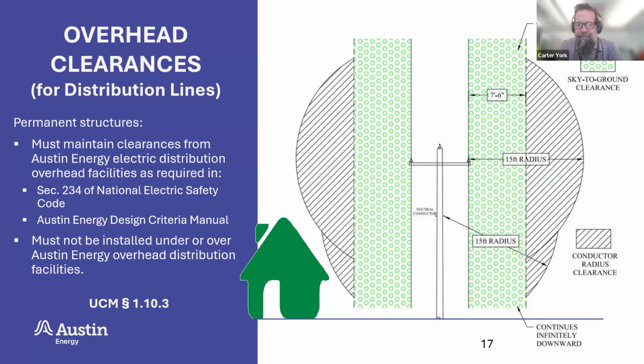Let's look at the image on the right. This is showing one of our utility poles in the middle. It has 3 conductors represented by the 3 small nodes at the top. That arm stretching across, supporting those exterior conductors, is 8 feet wide in a standard setting. And so our clearances are measured from the furthest conductor. And in this case, with 3 conductors, it's the outside conductor on either side. We have 2 clearances that we're looking at. One is a horizontal clearance, and that is 7 feet 6 inches laterally from the furthest conductor. That's represented by the green polka dot columns just to the outside of that pole arm at the top. And that goes ground to sky. Everything must be outside of that green polka dot area.